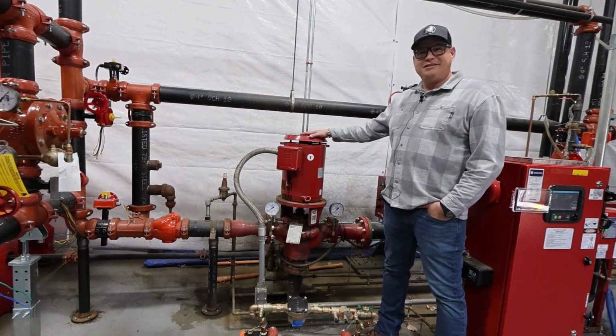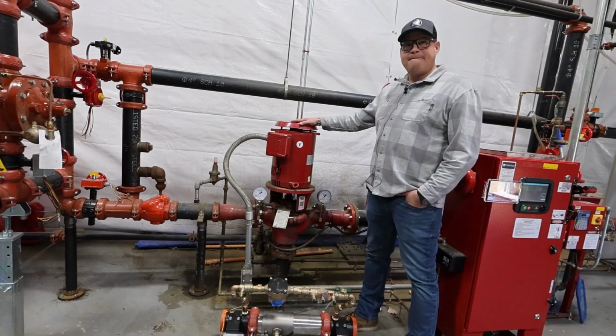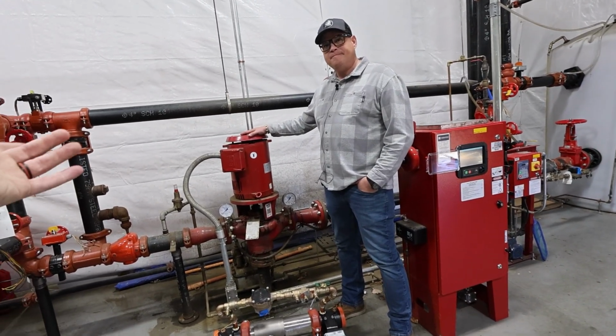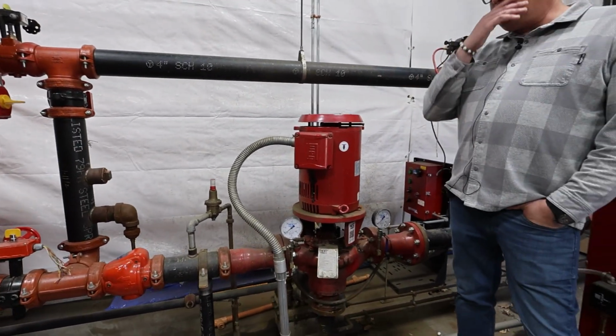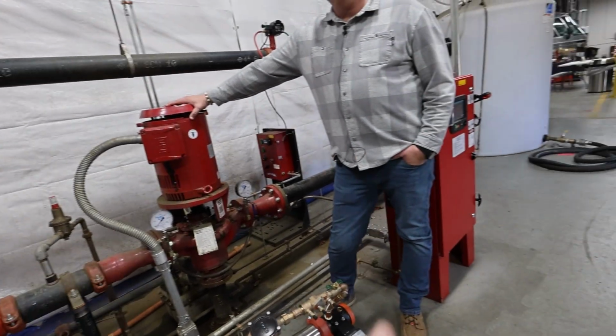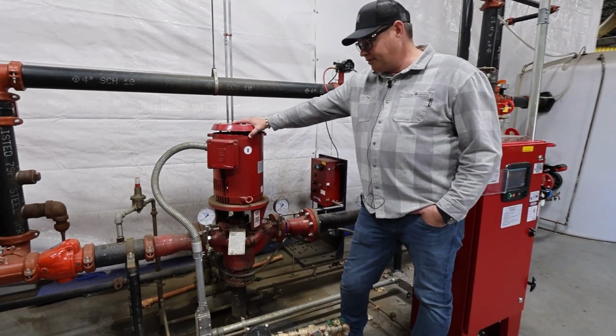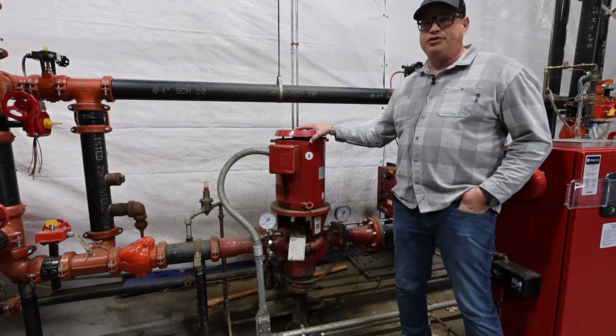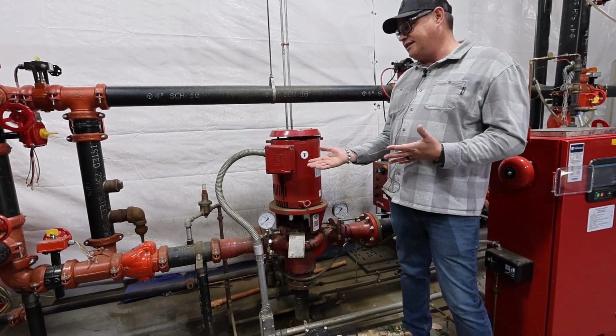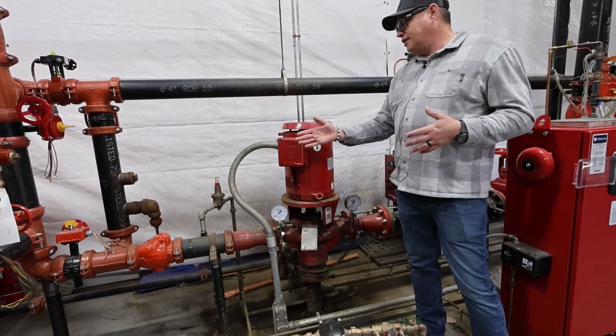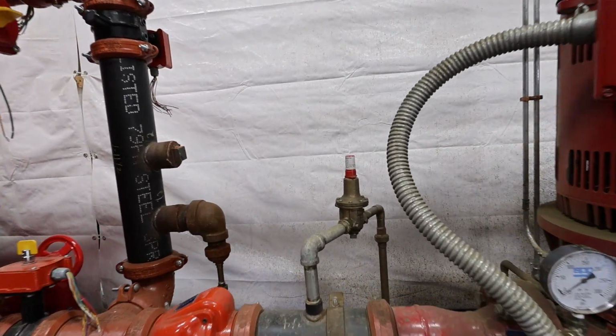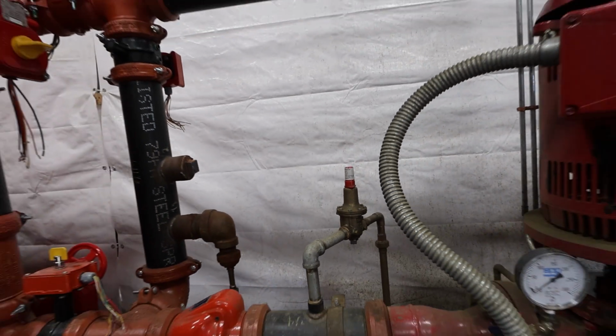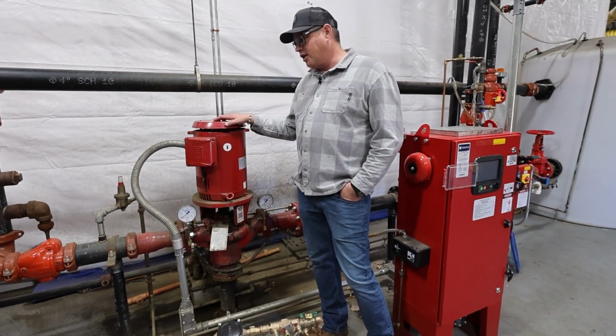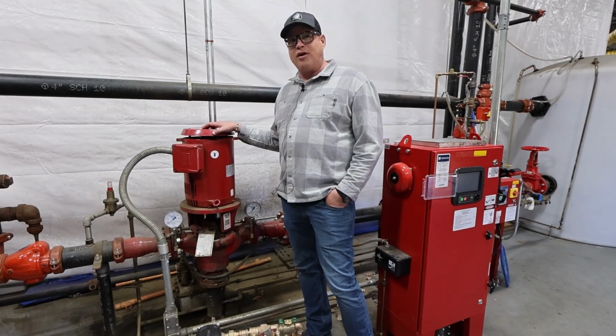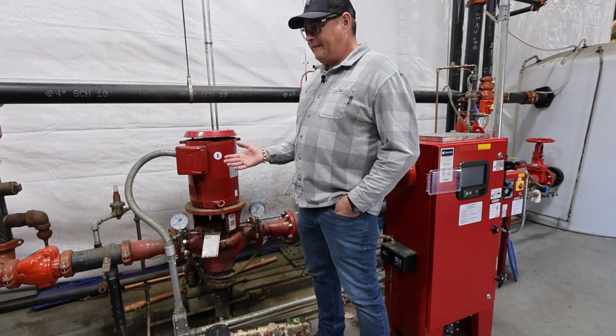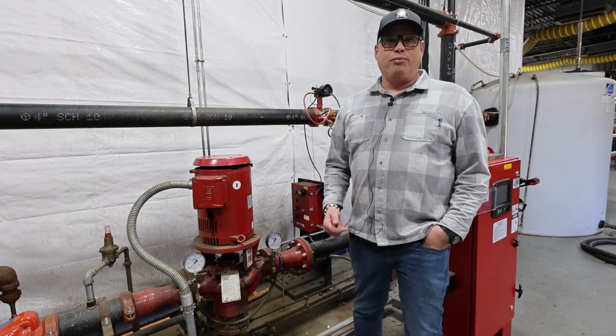Getting back into the fire pumps, when you kick that fire pump on, you also want to make sure your circulating relief valve is rolling. Start the pump, make sure it's kicking water. If you don't have water coming out into a drain, you've got a problem, maybe you need to replace your casing relief valve. If you've got one like this, that's a Cla-Val, these things will last forever. So you just want to check your settings, make sure you've got steady water flowing out, not a trickle, not a drip, but steady water coming out. And you want to make sure the drain it's going to is sized appropriately for that water.